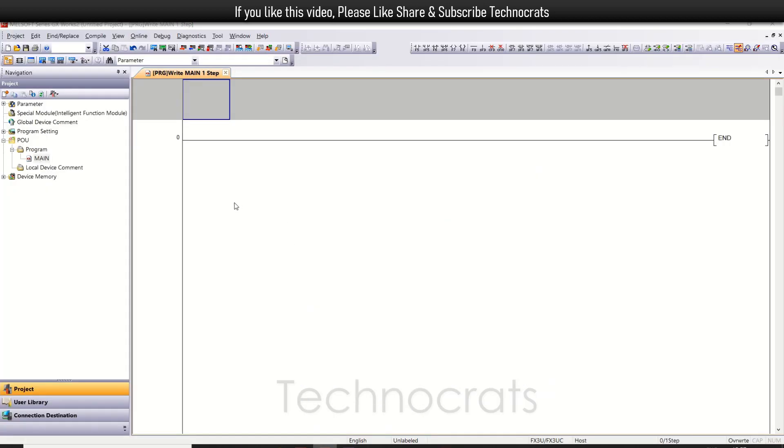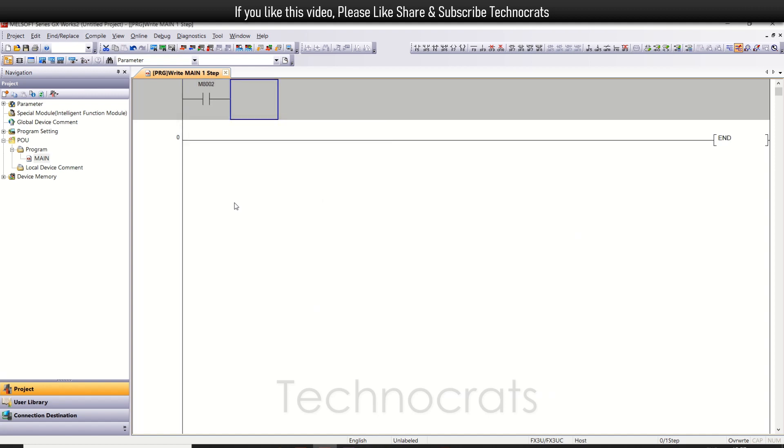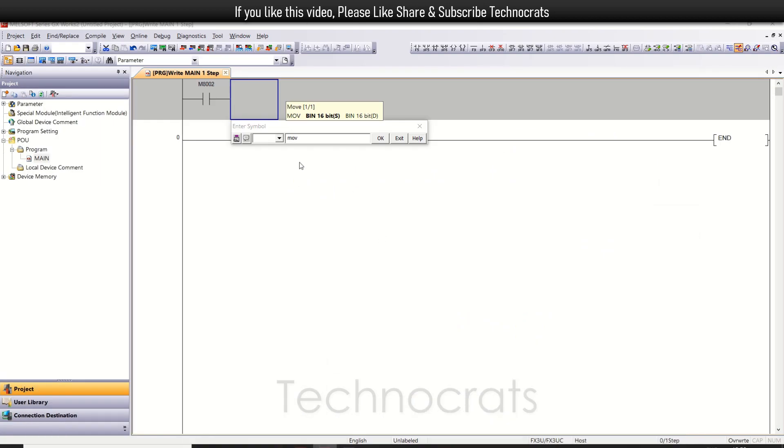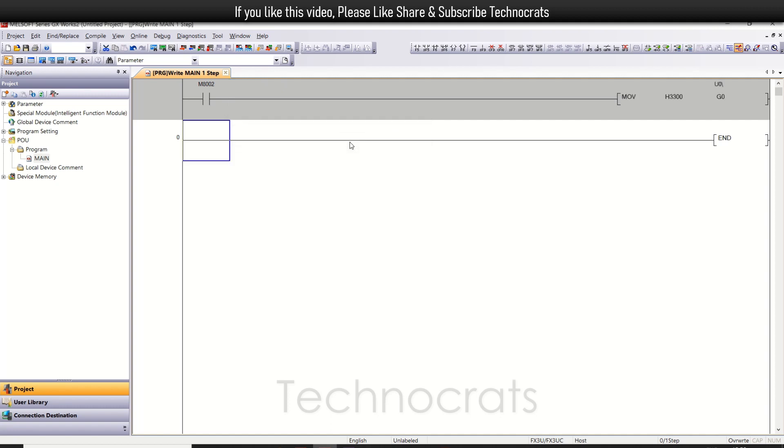So let's do the programming part. M8002, that is the single first scan bit. Now use the MOVE instruction. Let's make channel number 1 zero, which is voltage input, and channel 2 is also voltage input minus 10 to plus 10. Channel 3 is current input mode and channel 4 is also current input mode. So I will write H3300, and the buffer address is U0\G0, buffer value zero.